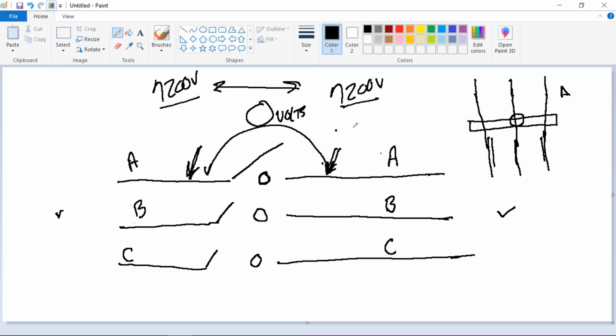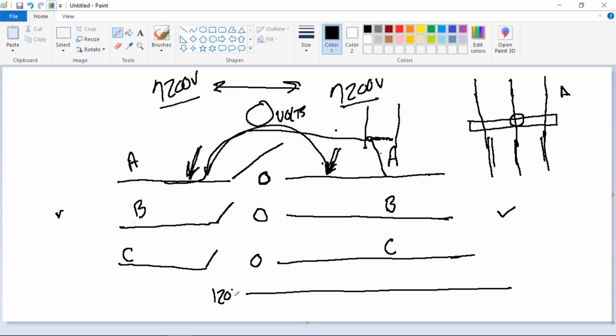Essentially, with the sticks, remember it had the cord in between. Here's your stick, and here's your stick, and the cord in between. There's no difference in potential. You're just making a continuation of a circuit. This is A, 7,200. This is A, 7,200. It's like taking a voltmeter on a piece of secondary wire, one wire that's hot, and putting both leads on the same wire. What kind of voltage are you going to get? 0. Here's my wire. I put 120 volts on it. I put a lead on this end, it's got 120 volts, and I put a lead on this other end, it's got 120 volts. How many volts am I going to read on the meter? Same wire. 0. There's no difference in potential.